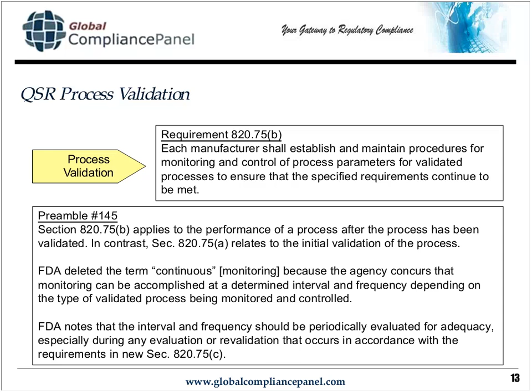Now, 820.75c talks about changes or process deviations, and process deviations are one of the issues we want to talk about. The process input parameters could go outside the acceptable limits—parameters change over time due to natural variability of the process. If they go outside the acceptable limits, we don't know that we've got a process operating with a high degree of assurance. So why did that happen? What went wrong that allowed that to happen? That would be a process deviation—a verification check reveals a problem.